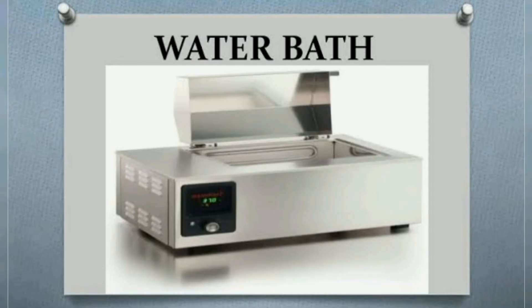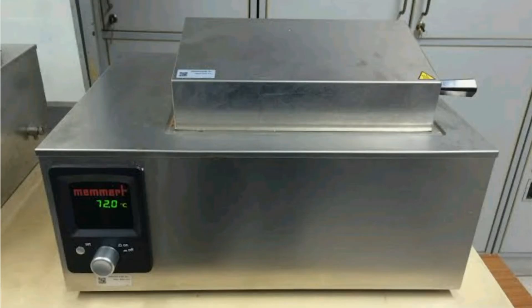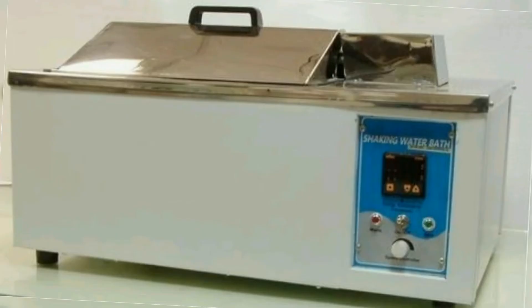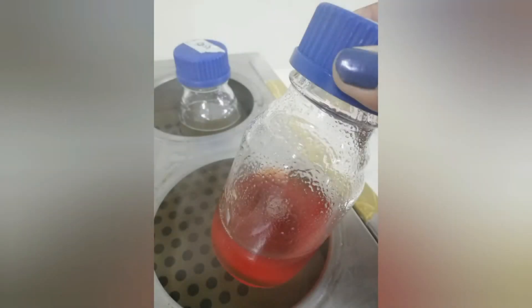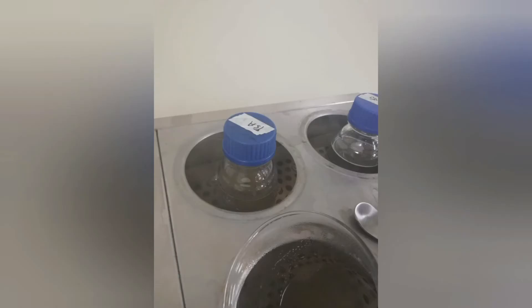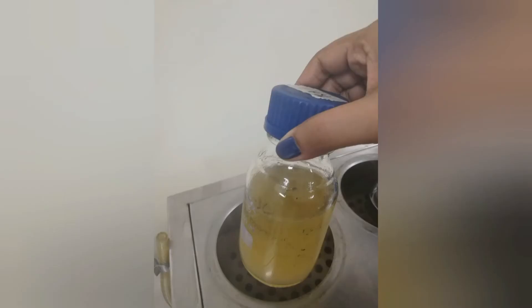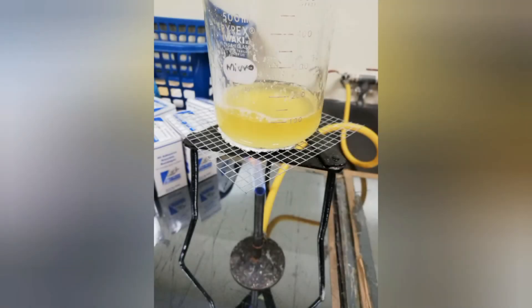A water bath is laboratory equipment made from a container filled with heated water. It is used to incubate samples in water at a constant temperature over a long period of time. It is also used to provide heat and dissolve solutions or media during preparation. We also use this equipment for endotoxin testing, to give a specific temperature to the vial.